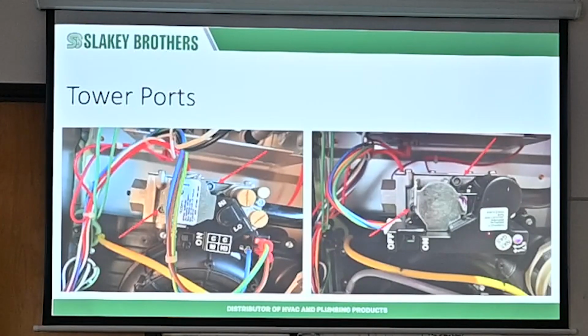It's because it tripped on the high limit at a low or medium rate. Okay? But again, a modulating furnace will never ever trip, will never ever overheat. A two-stage furnace, same thing. Once you set the low and high, it's the same thing.